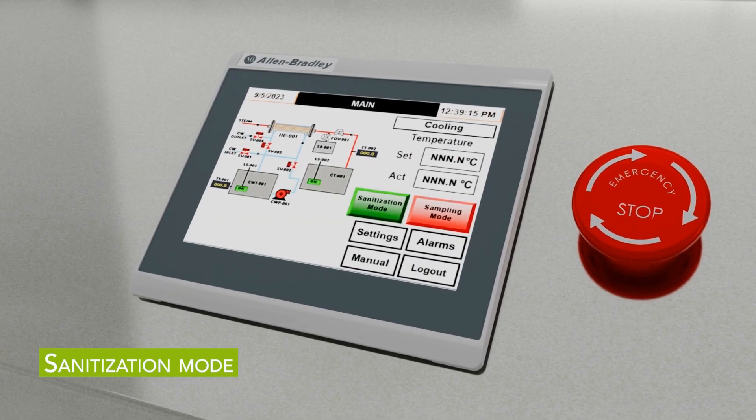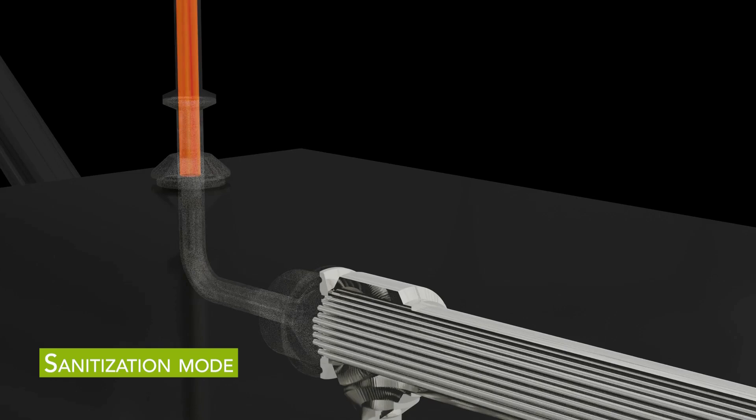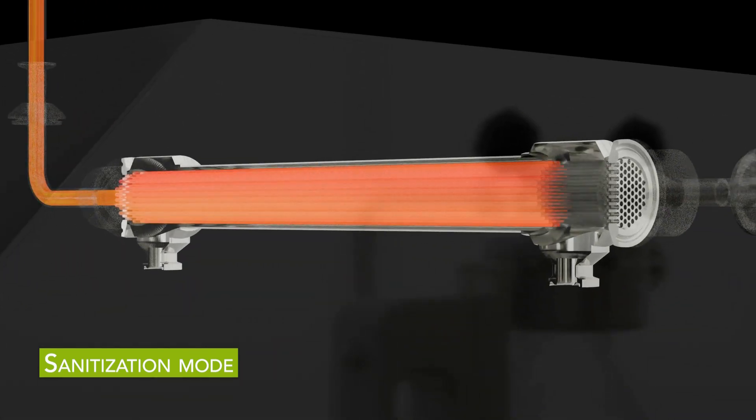During sanitization mode, clean steam is passed through the heat exchanger and sample valve, sanitizing the system prior to sampling. Any steam condensate is safely collected in the onboard waste tank.